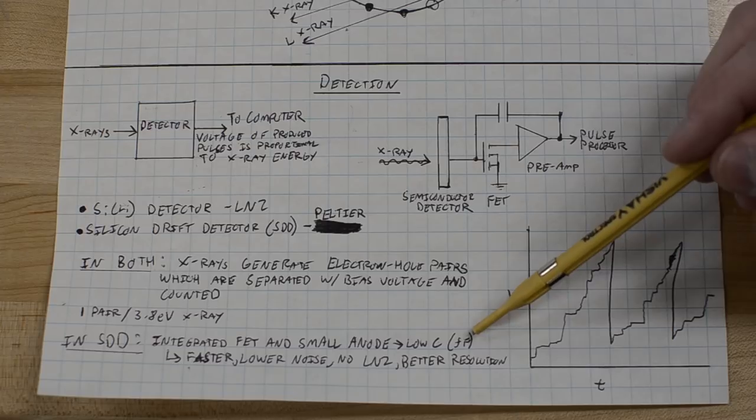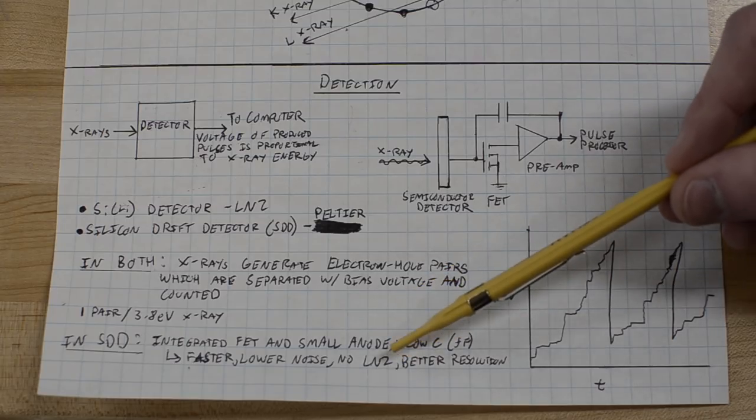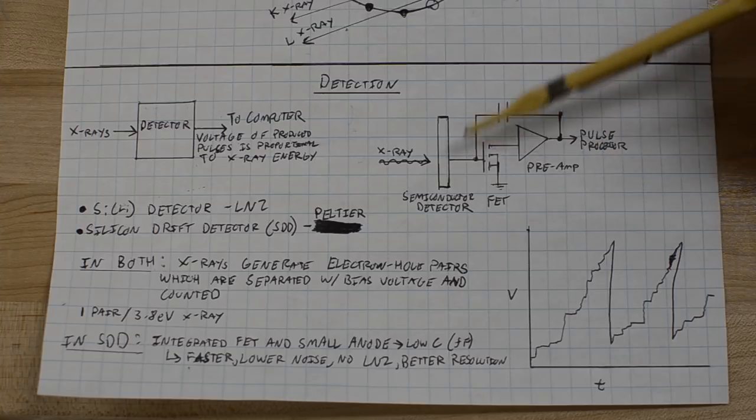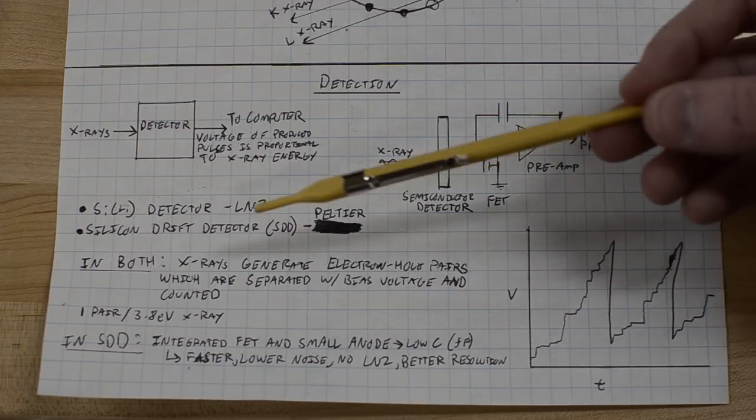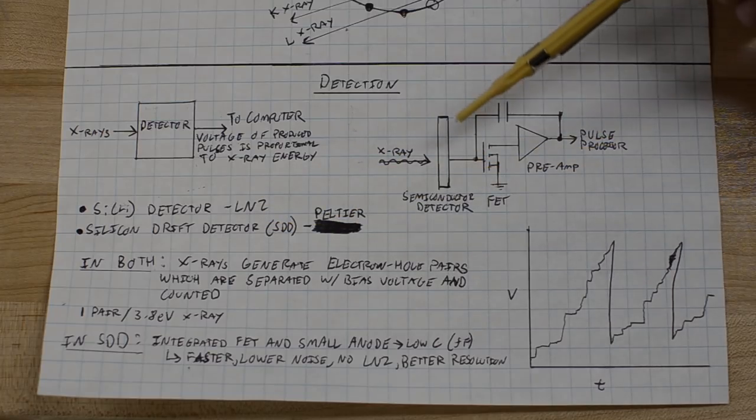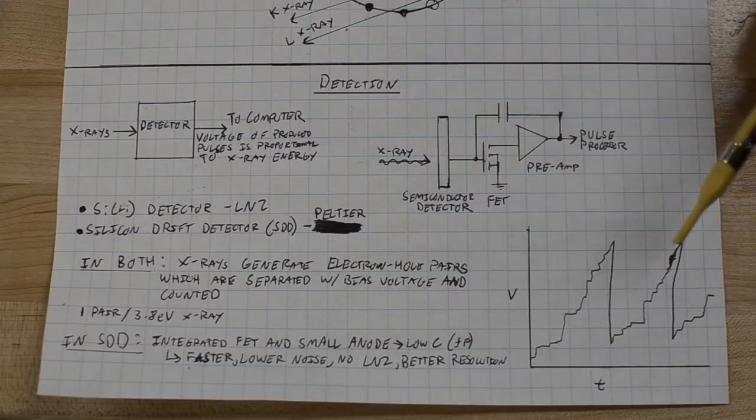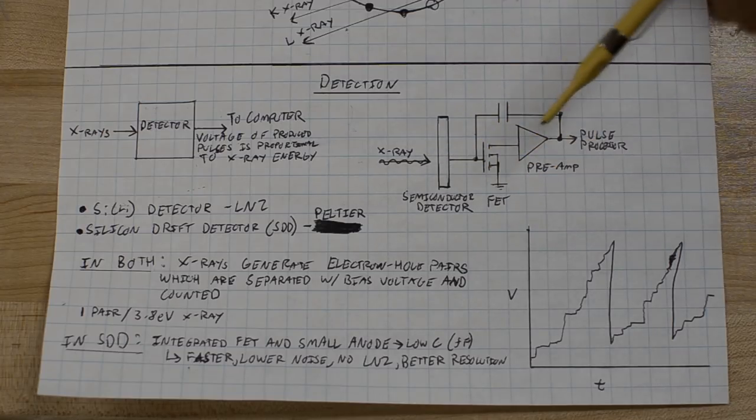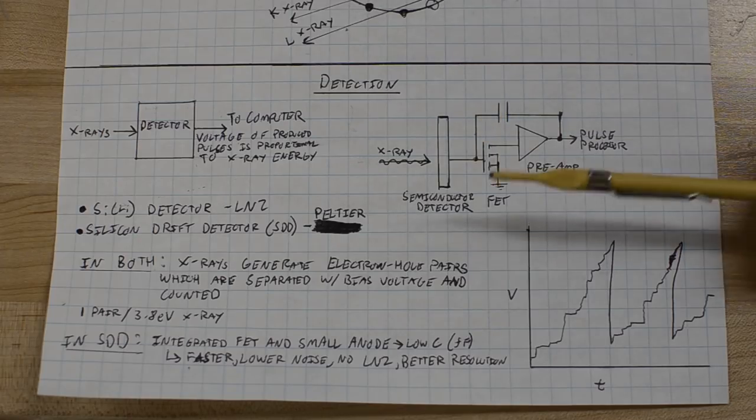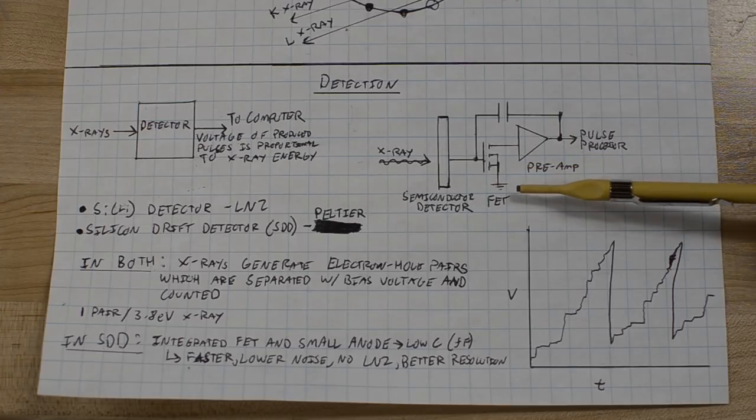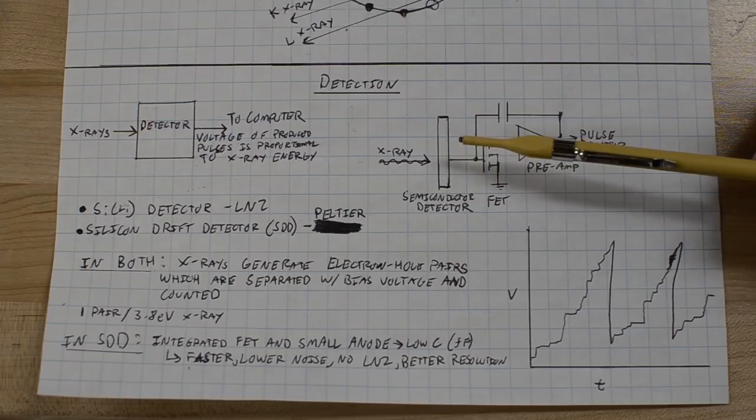That smaller collection site allows you to have a much smaller device capacitance overall. This is in the range of maybe 50 to 100 femtofarads. And that leads you to better performance, lower noise, faster detection, you don't need the liquid nitrogen cooling, and better resolution. Overall, it's just a nicer detector. The electronics outside of the semiconductor detector are basically the same. The x-rays hit the detector, and the detector gives off pulses for each individual x-ray event. We're actually counting individual pulses here.